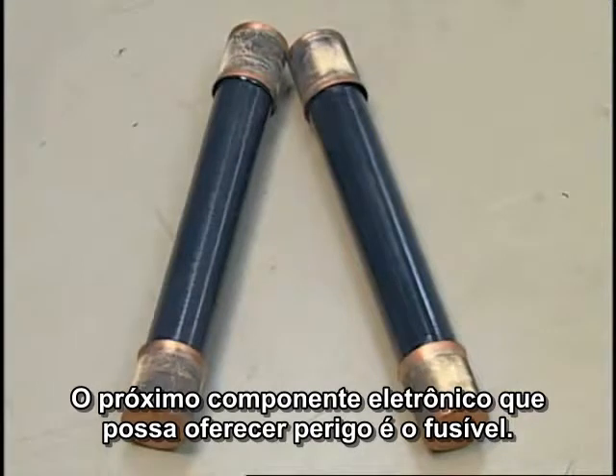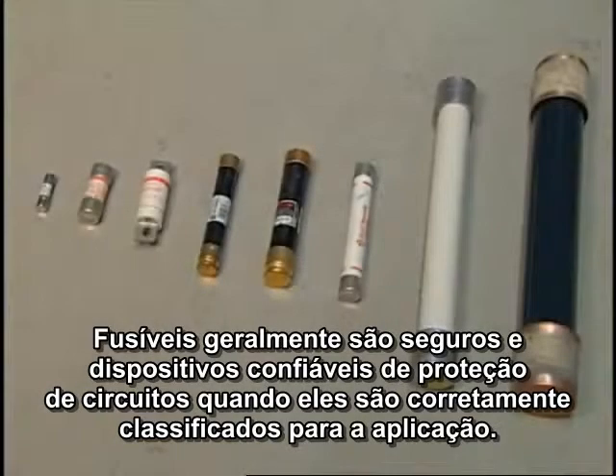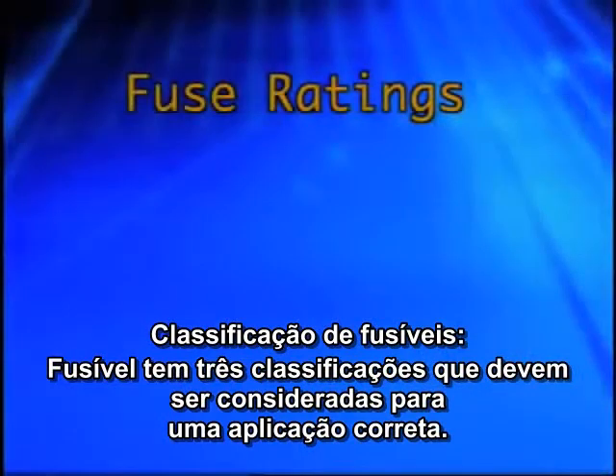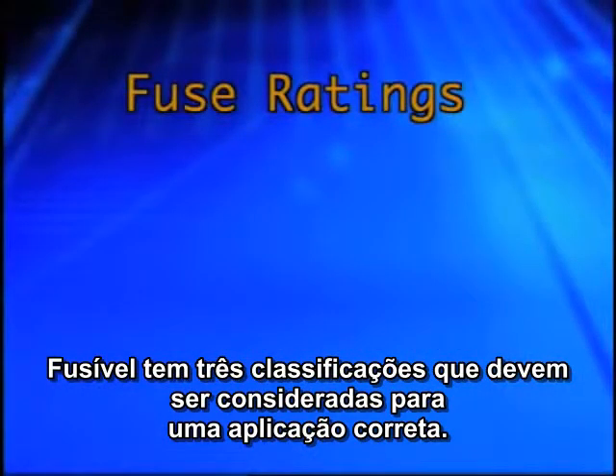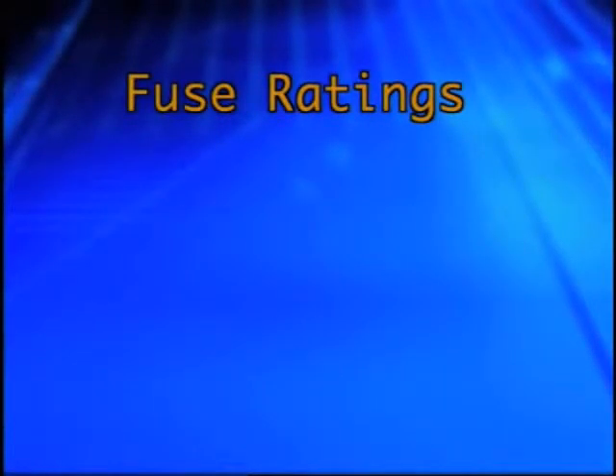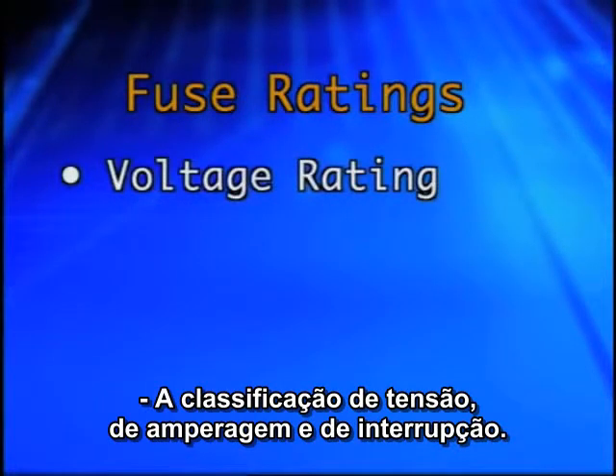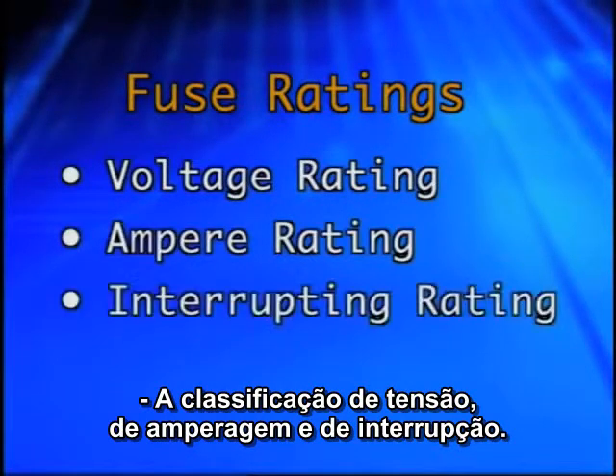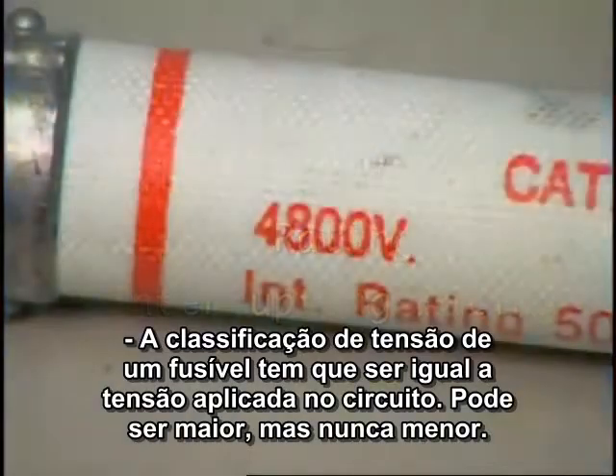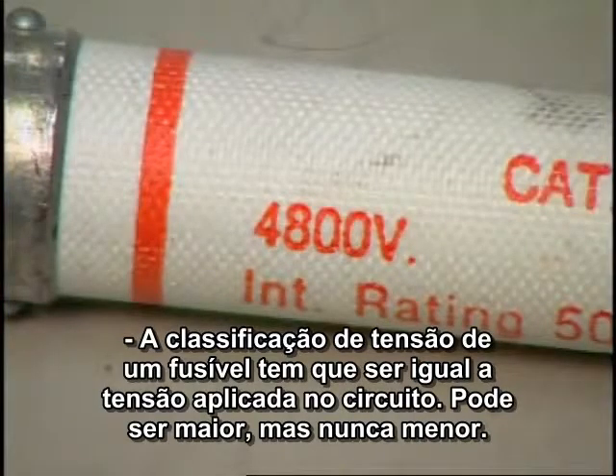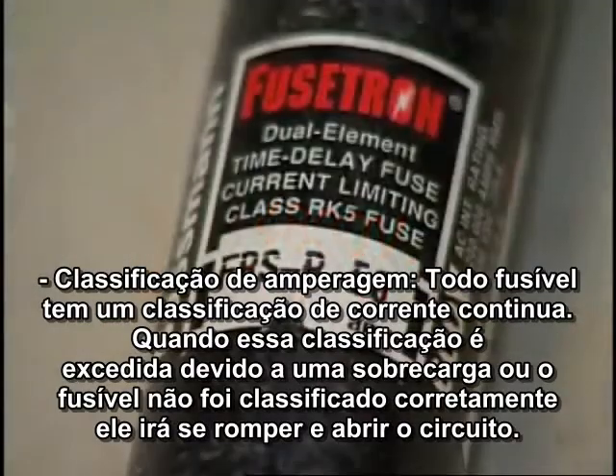The next piece of electrical equipment that carries possible hazards is the fuse. Fuses are generally safe and reliable circuit protective devices when they are properly rated for the application. A fuse has 3 ratings that must be considered for proper operation: the voltage rating, the ampere rating, and interrupting rating. The voltage rating of a fuse must be at least equal to the applied circuit voltage. It can be higher, but never lower than the circuit voltage.